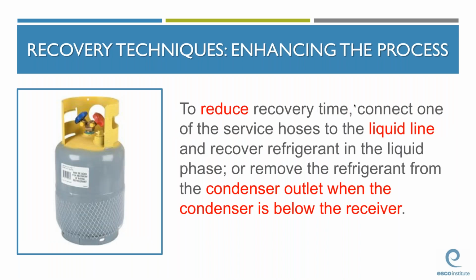Since liquid refrigerant is more dense than vapor, liquid recovery is faster than vapor recovery. So liquid recovery is initiated by connecting the service hose to the system's liquid line. To remove the most liquid refrigerant from a system, the service hose should be connected to the lowest part of the system known to contain liquid. For example, if the condenser outlet is located below the receiver, it's best to recover liquid refrigerant from the outlet of the condenser. So we want to recover from the lowest point known to contain liquid.